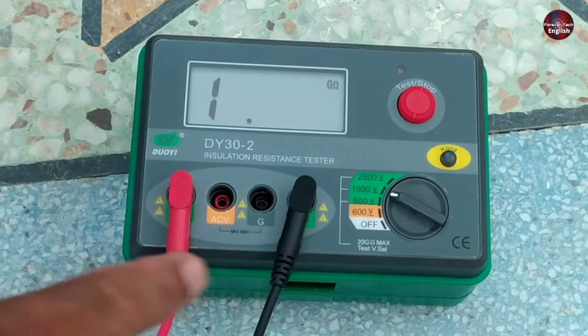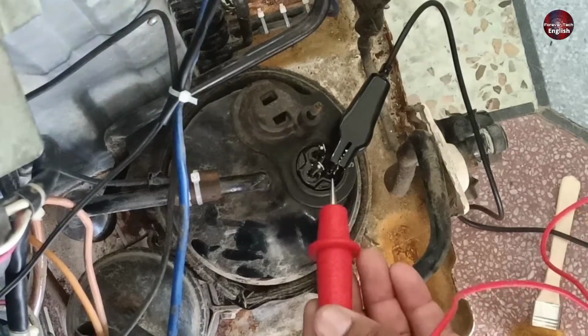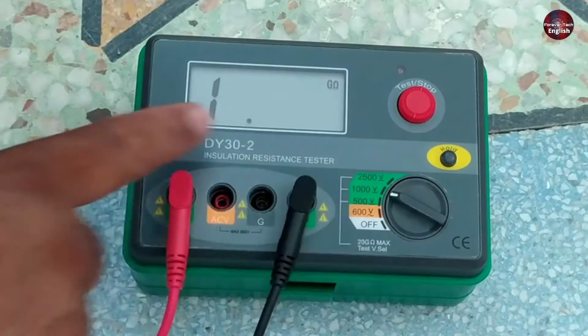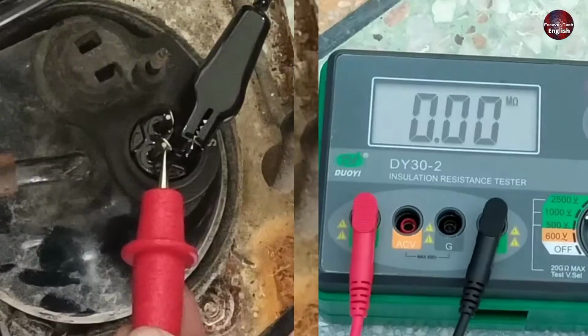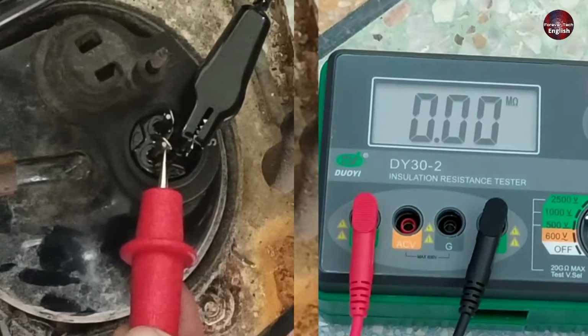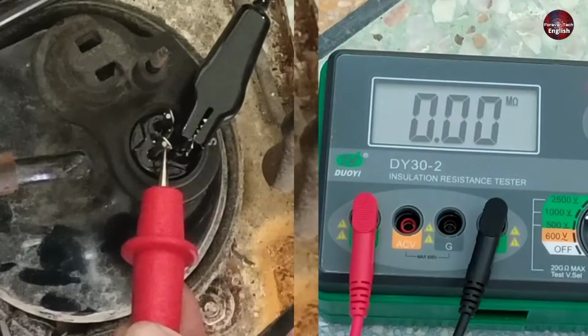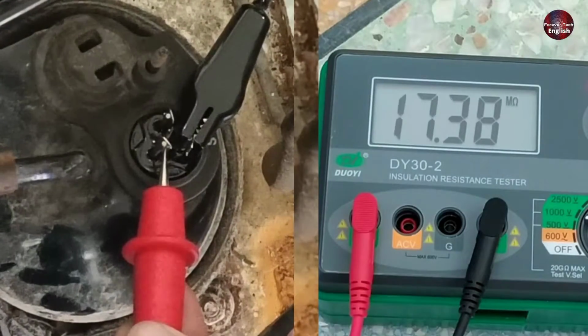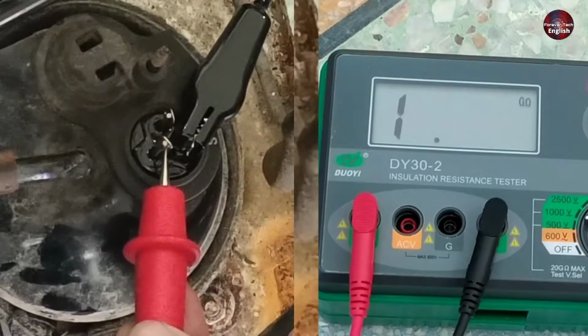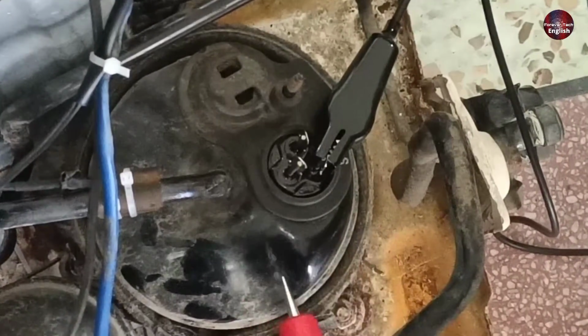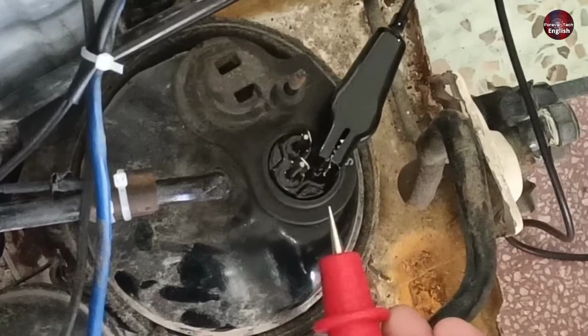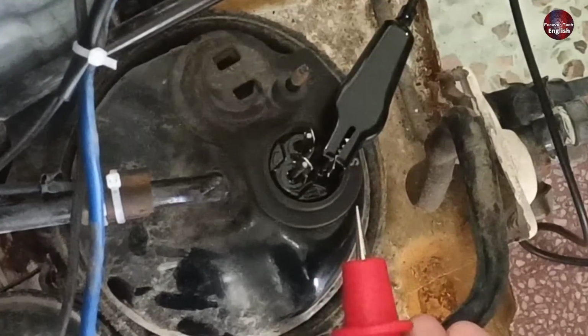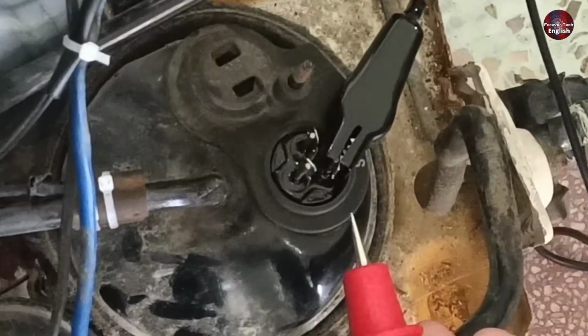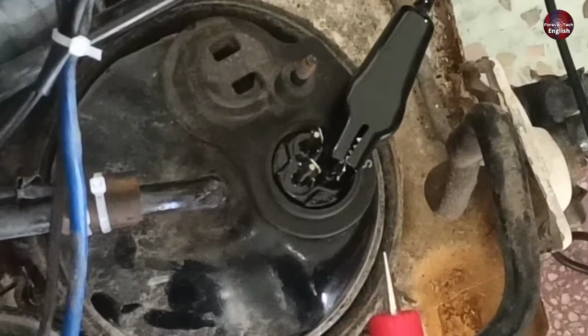I will also tell you its reason, but first, I will show you how to test the compressor. I have pressed the test button. And see, it is showing 0.00 mega ohms on the terminals. This means the coils inside the compressor are not disconnected. The main benefit of compressor testing is to check the insulation with the compressor body and whether it shows resistance with the body. And try not to touch your hand on the body, as they are high voltages.